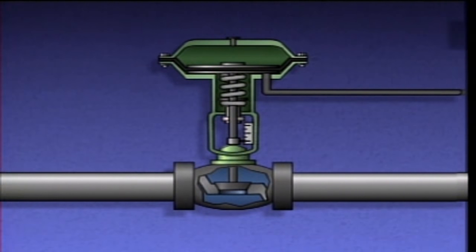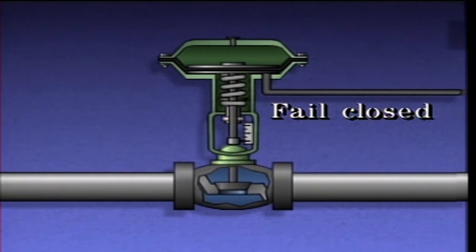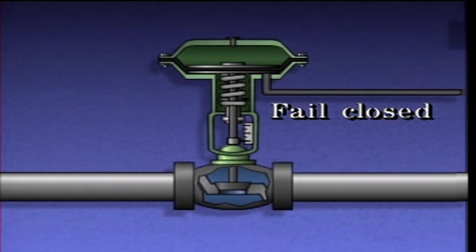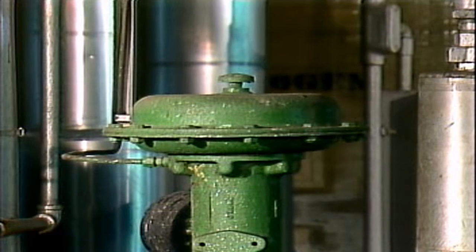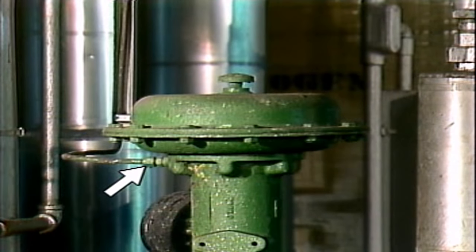A control valve using this kind of actuator is said to fail closed because if air pressure is lost, the spring in the actuator will close the valve. A diaphragm actuator with an air line to only the lower chamber is typically an air-to-open, spring-to-close type.